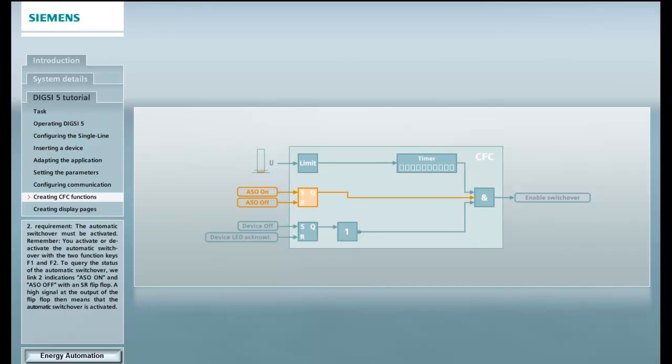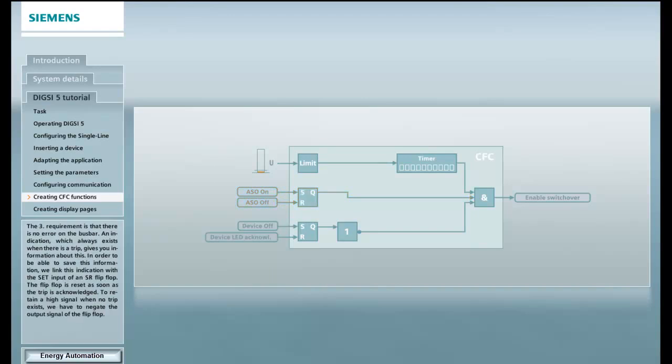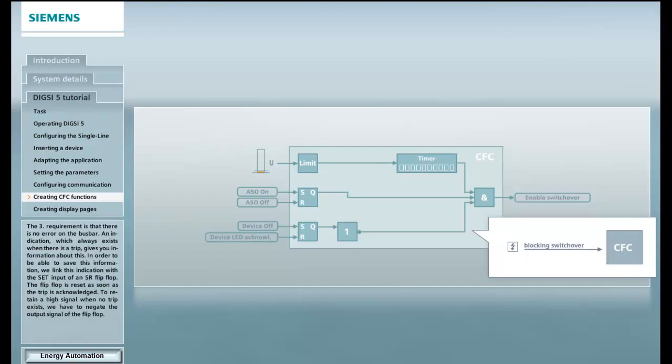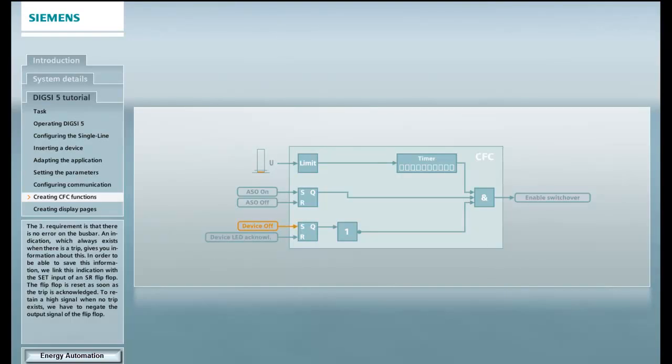A high signal at the output of the flip-flop then means that the automatic switchover is activated. The third requirement is that there is no error on the bus bar. An indication which always exists when there is a trip gives you information about this. In order to be able to save this information, we link this indication with a set input of an SR flip-flop. The flip-flop is reset as soon as the trip is acknowledged. To retain a high signal when no trip exists, we have to negate the output signal of the flip-flop.